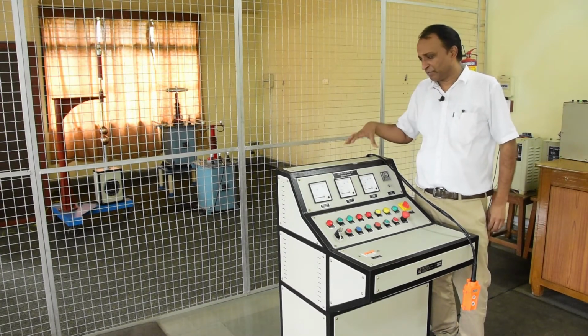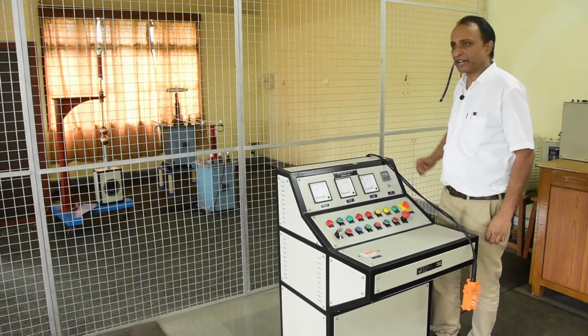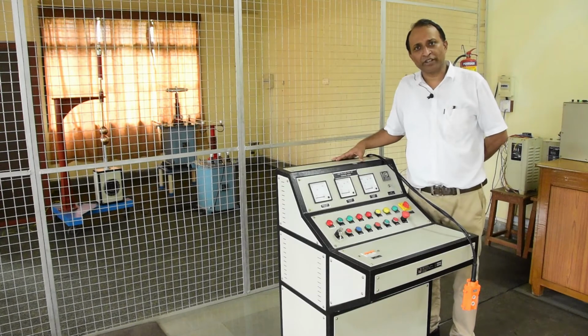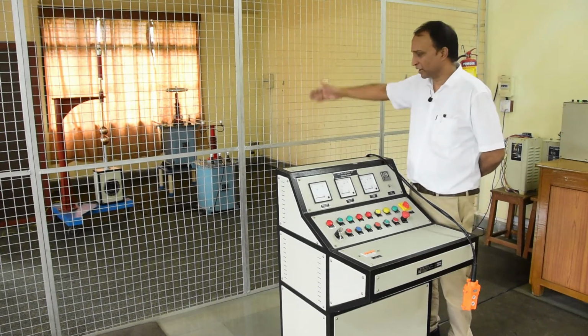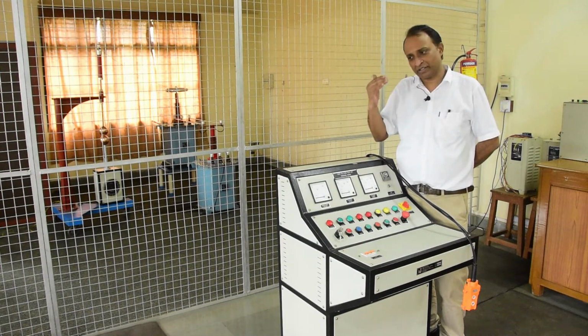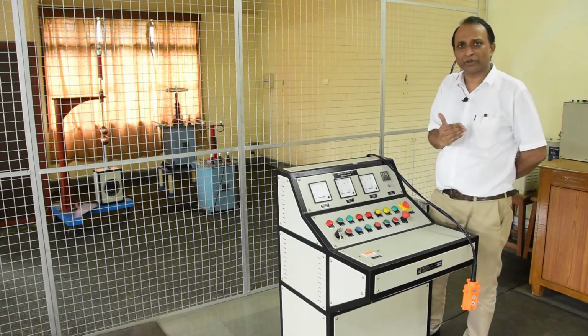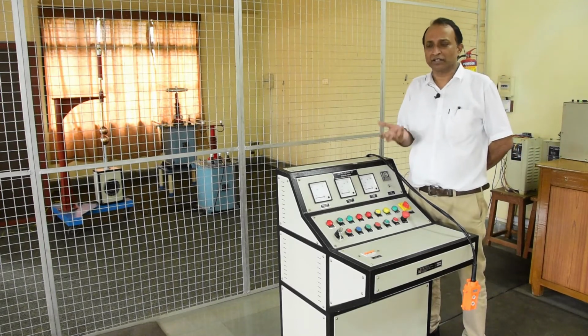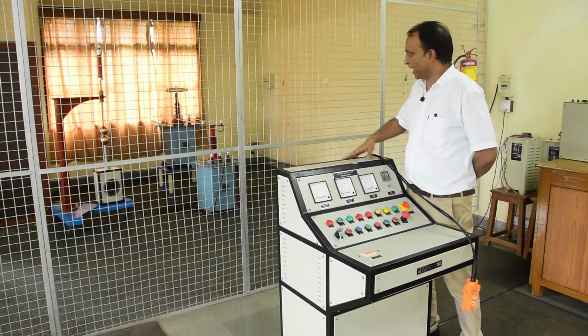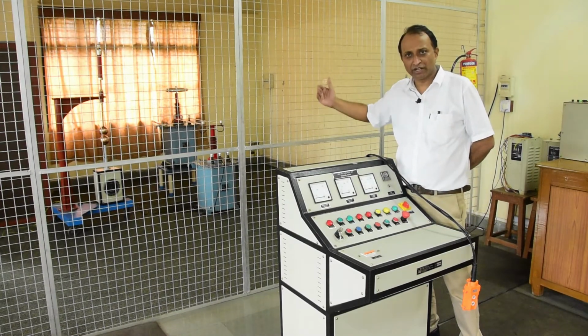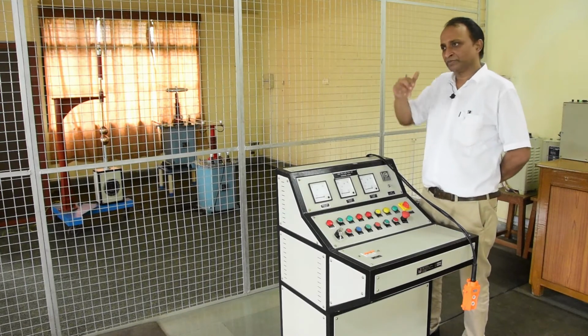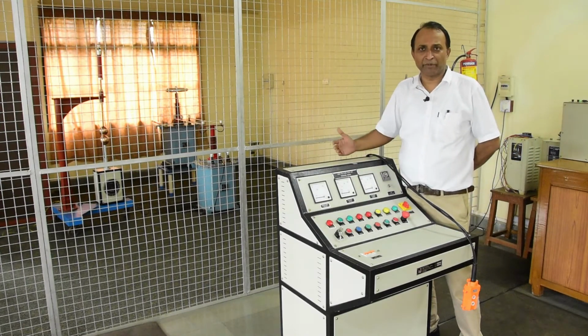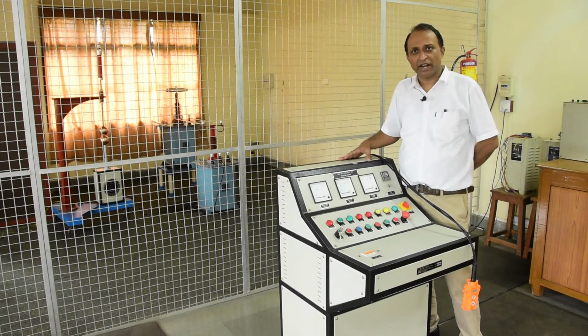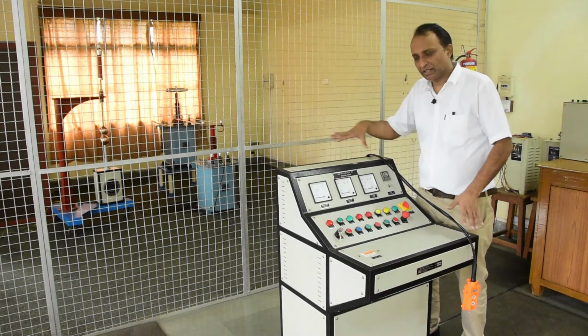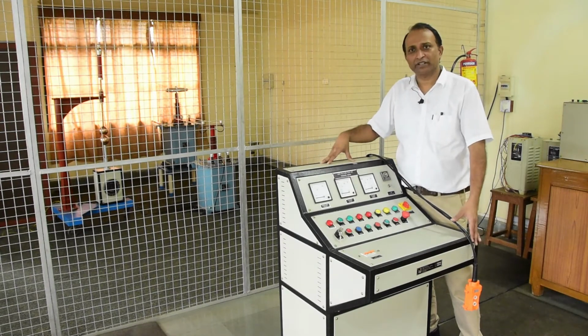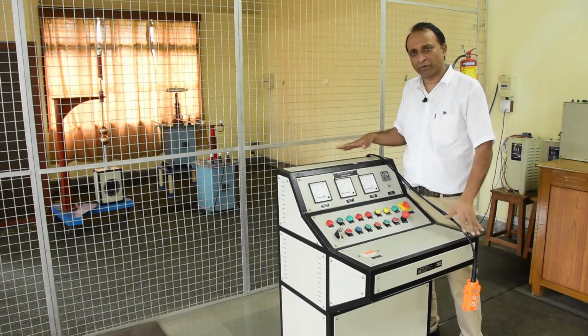So naturally, the method adopted here is known as a sphere gap. There is a standard breakdown strength of an air gap across spherical electrodes, which is categorized as a reference, and it can be used for calibrating a voltmeter. So what we do is adjust the spacing between the electrodes to a standard distance, let us say 1 millimeter, 2 millimeter, 5 millimeter, 7 millimeter, or 1 centimeter, and corresponding to that spacing we apply the unknown voltage which is to be calibrated for measurement using this particular control panel.